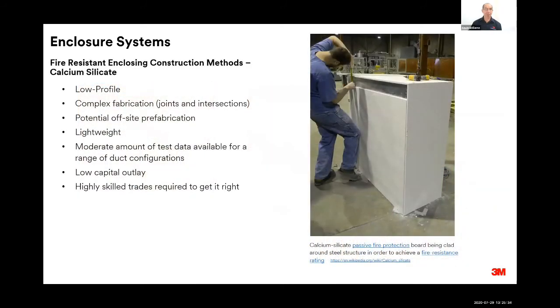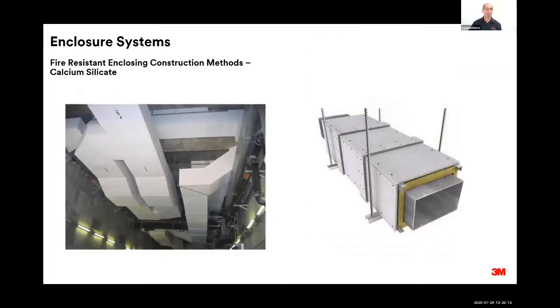Another method is using fire-rated boards, calcium silicate boards, for example. Again, they tend to be low profile, and can involve complex fabrication because of all the joints and intersections. There is potential for lightweight off-site prefabrication, but again, it's a rigid system, so you need to be careful about not cracking it and putting too much stress on it in transport. Fairly lightweight. There's a moderate amount of test data available for a range of configurations. Low capital outlay, but it generally requires high-skilled trades to get it done properly, and it can look quite good installed. So there's a couple of pictures there. In some cases, it might be a combination of the calcium silicate board on the outside with some high-temperature insulation on the inside.